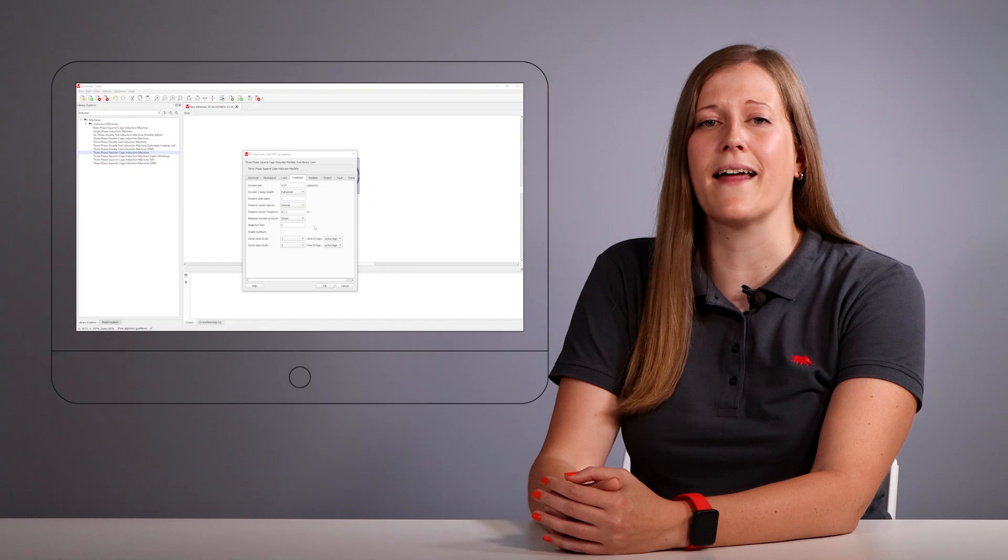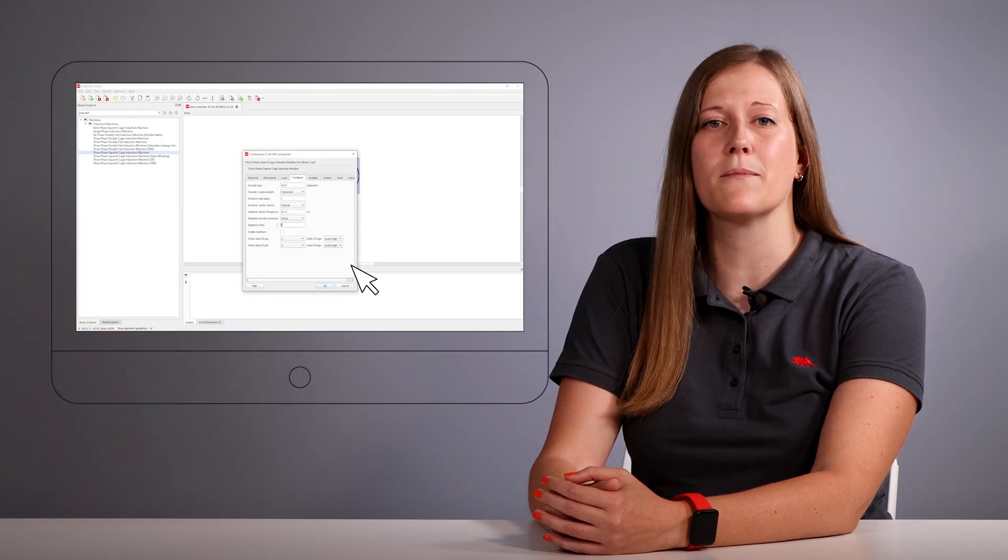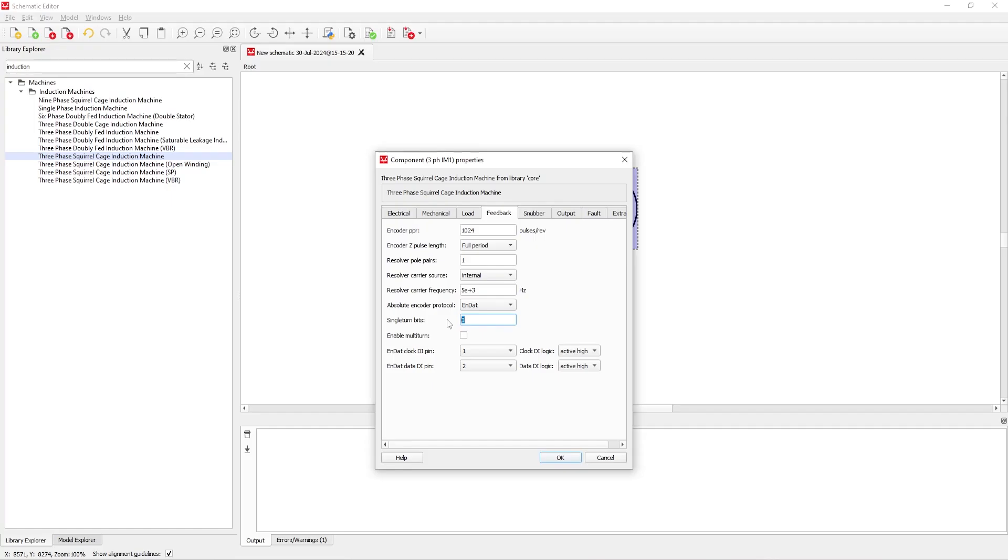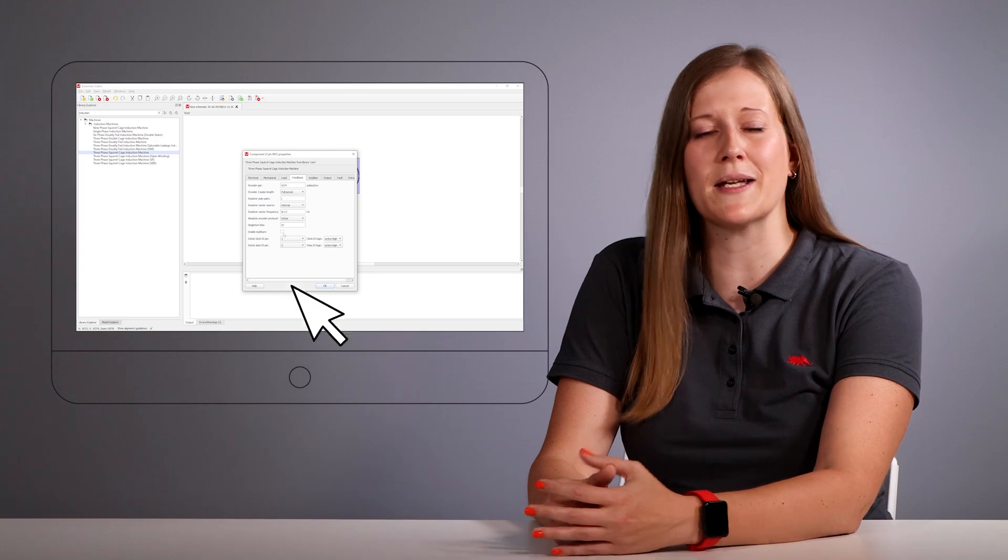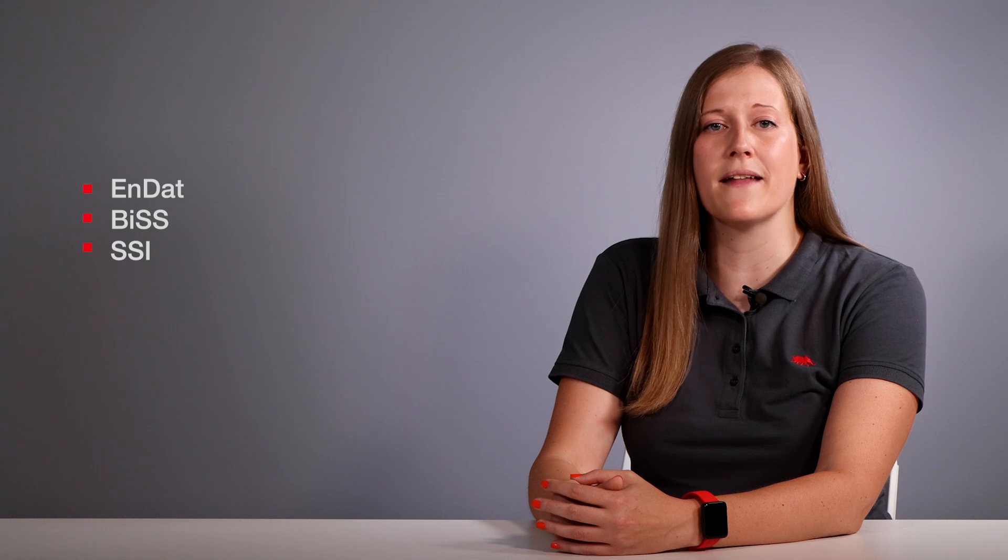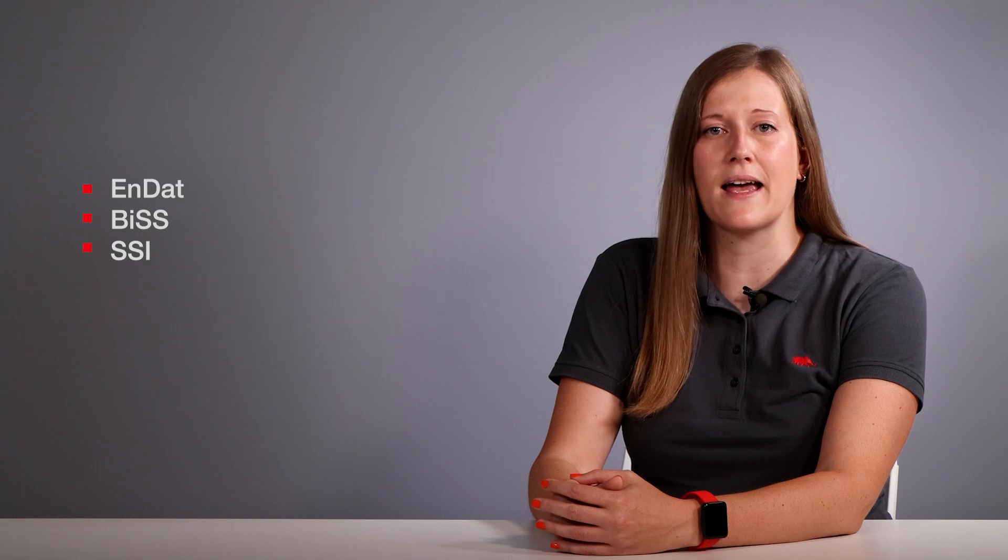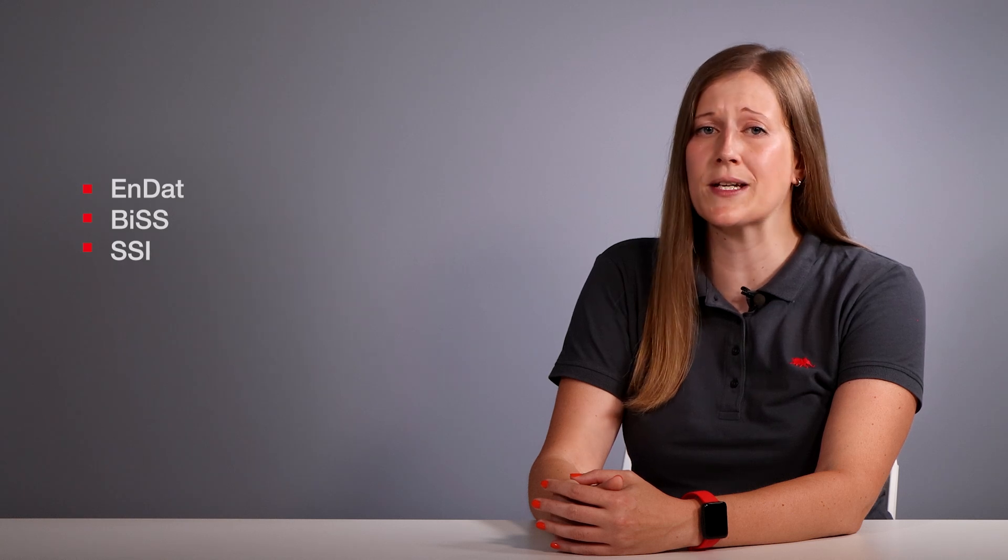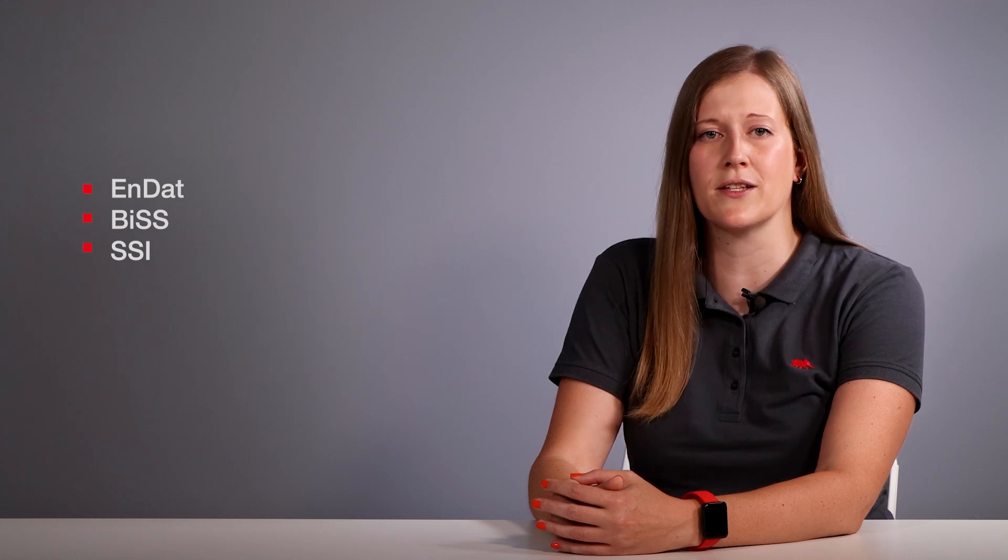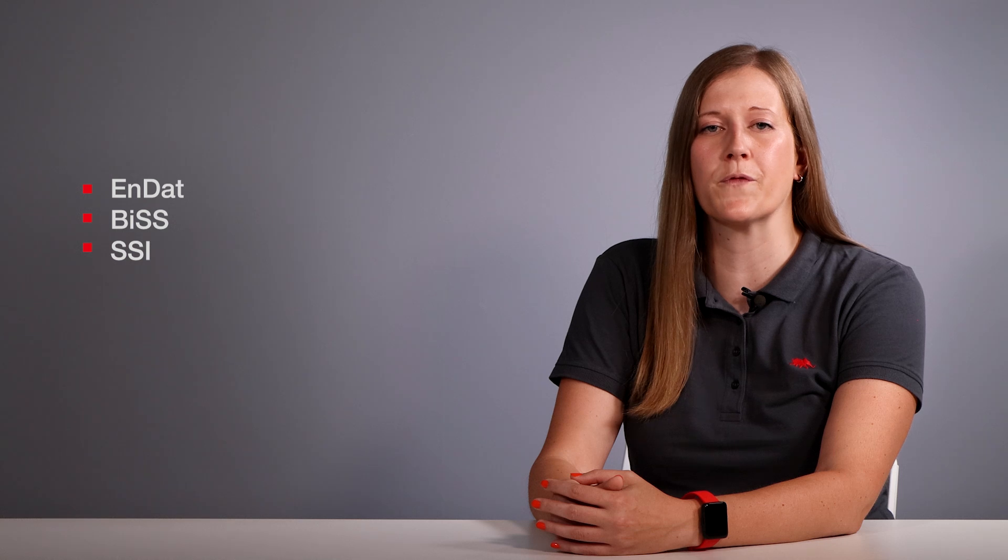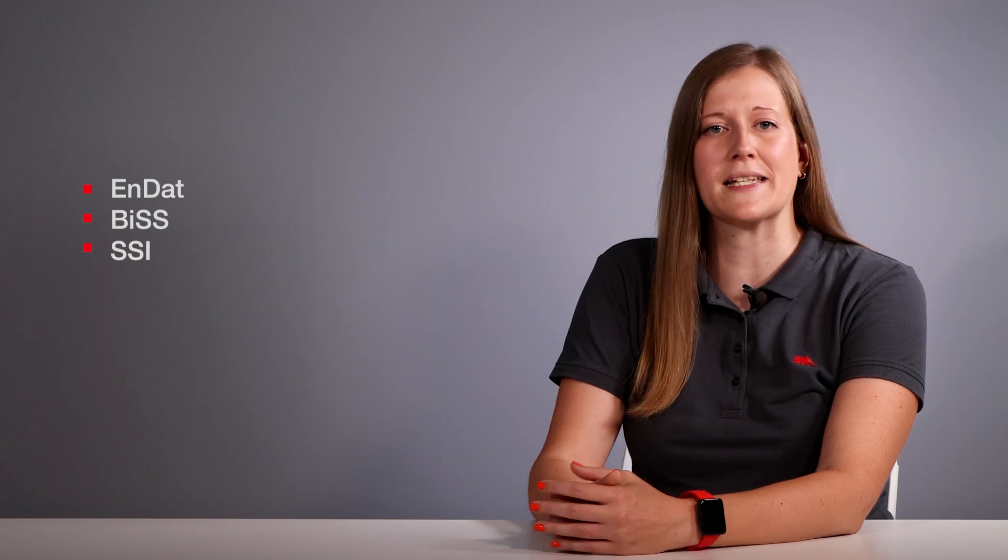Previously, the encoder data length was limited to 16 bits, but now you can use different encoder data lengths to suit your specific needs. We have also added the option to specify the number of multi-turn bits, providing more detailed and accurate tracking. These enhancements are available for EnDat, BIS and SSI protocols, ensuring that your system can handle a variety of encoder configurations with improved flexibility and precision.